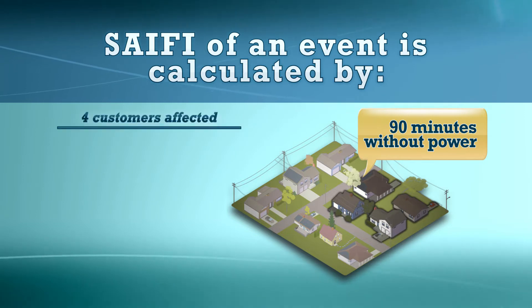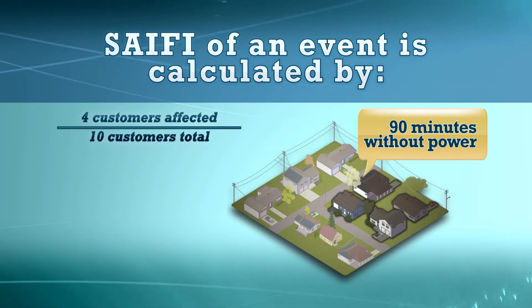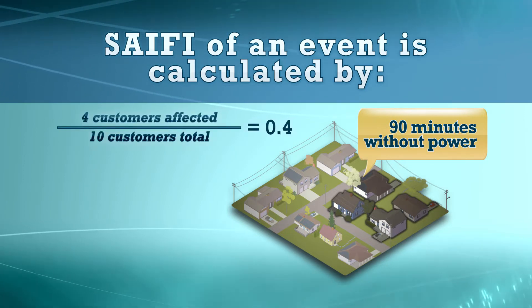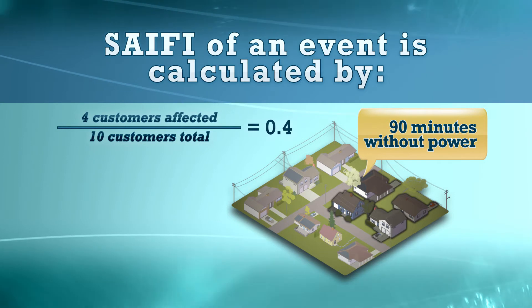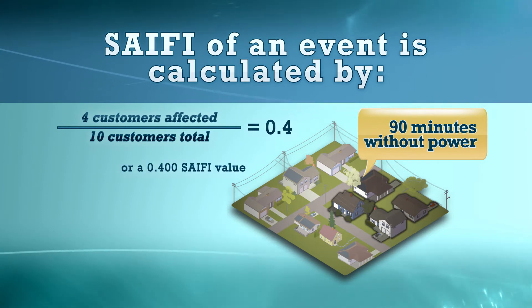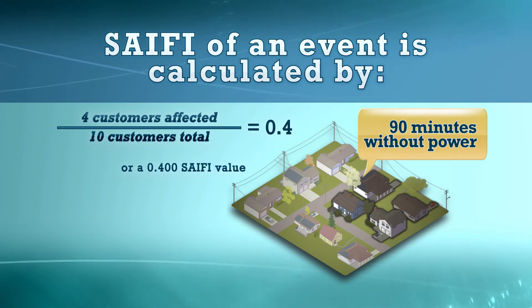Suppose in a small grid of 10 people, a tree falls on a power line and causes four people to lose power for 90 minutes. In this instance, four customers were affected out of ten customers total, and we get a value of 0.4, or a 0.400 SAIFI value.